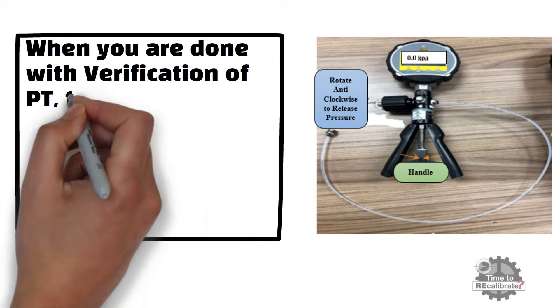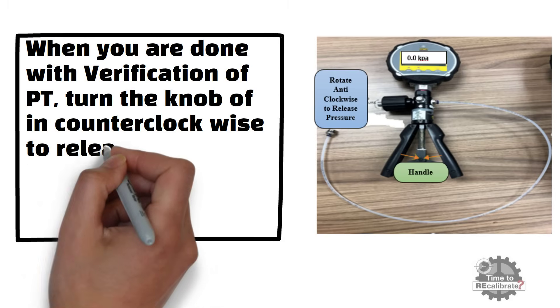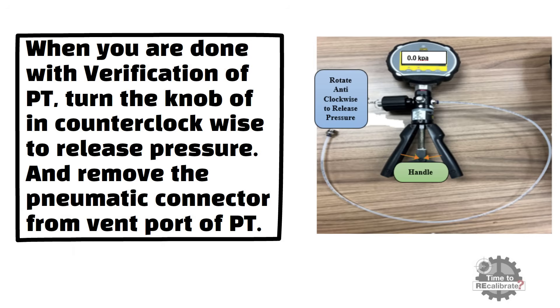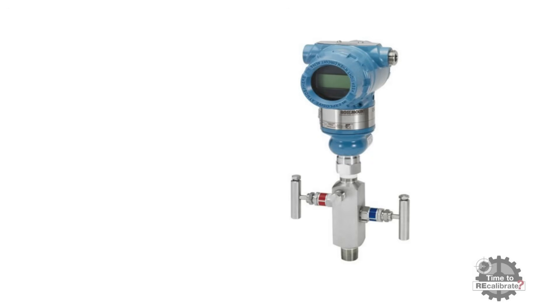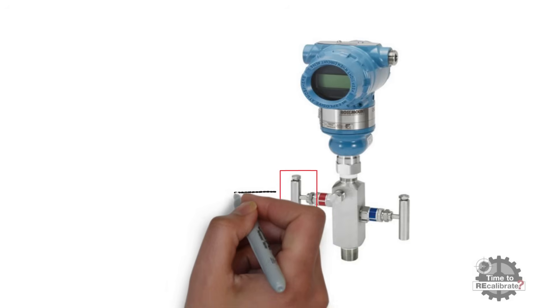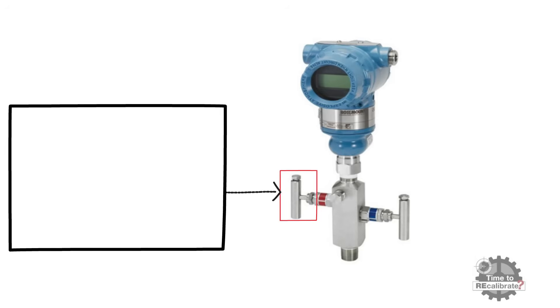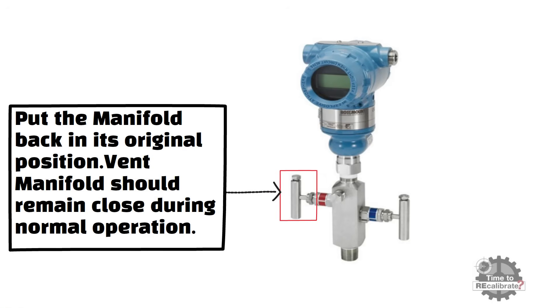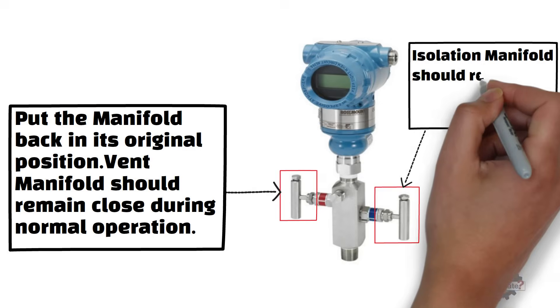When you have finished verification of the pressure transmitter, turn the little knob of the pressure calibrator anticlockwise in order to release the pressure. Remove the 1/4-inch connector from the vent port of the pressure transmitter. Close the vent port of the pressure transmitter by using the original fitting. Now put the manifolds back in their original position. The vent manifold should remain closed during normal operation, and the isolation manifold should remain open during normal operation.